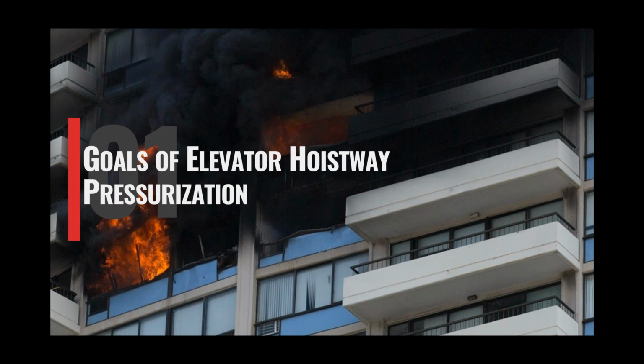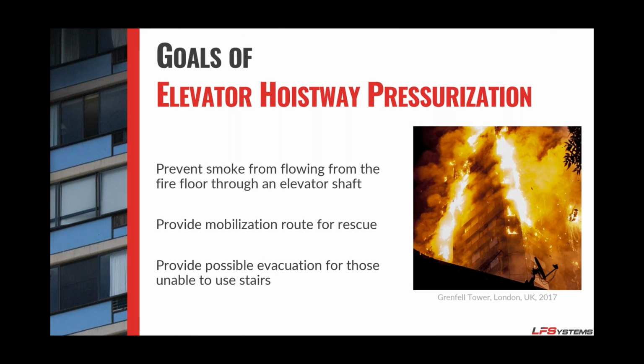So we talk about the goals of elevator hoistway pressurization. There's primarily three reasons we pressurize our elevator hoistways, and the primary one would be to prevent smoke from flowing from the fire floor to other floors through the elevator shaft. That's the main reason. No matter what kind of building you have, no matter what your evacuation plan is, you want to make sure that smoke doesn't get from A to B, right? But there's also the opportunity to use your elevators to mobilize first responders, and as an evacuation for those that are unable to use the stairs.